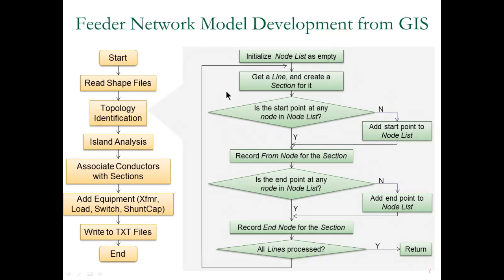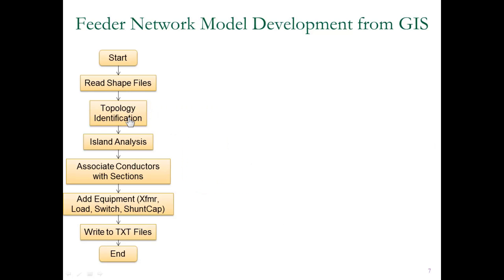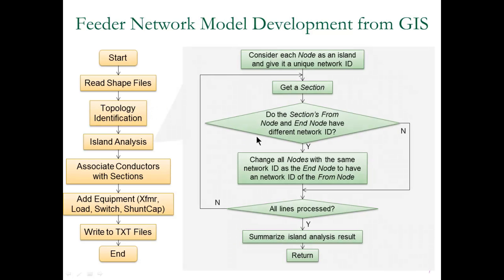So essentially, at the end of this process, we should have a complete list of all the nodes or the buses in the feeder and all the sections or branches connecting these various nodes, with each section having a unique from node and to node. That gives us the complete electrical connection of the different nodes. After finding all the nodes and sections, the next concern is to determine whether the identified topology is a single fully connected network. To do that, we need to go through this island analysis algorithm and make sure that the topology is a single fully connected electrical network and no small islands exist. Now, if there are islands, then we need to relook at all the switch positions.